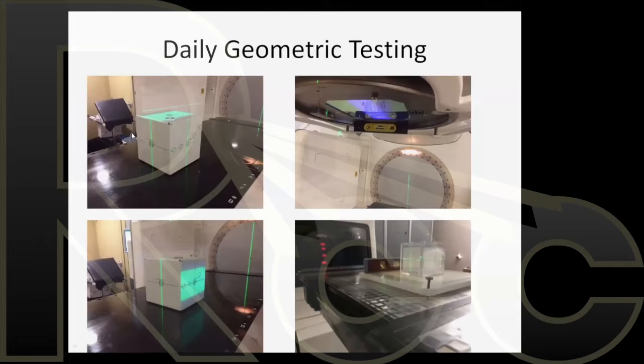So daily geometric testing with one of these guides, you place it on the table, you level it, and you set your isocenter at the crosshair, and you can check a field size on the top of it. We use a spirit level on the gantry to check gantry angles. And then as we rotate the machine around to a lateral position, does the crosshair agree with the laser? And we like to see that within 1 millimeter. Here is a homemade device that does the same thing, a cube with graph paper on it, and a leveling platform and a spirit level.